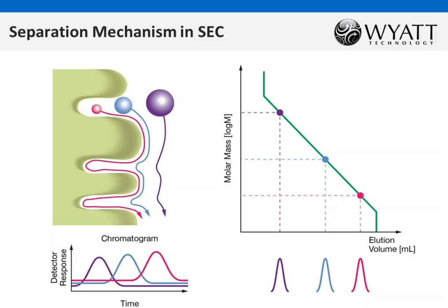Coupling SEC to multi-angle light scattering, however, overcomes this limitation. Since light scattering measures the absolute molar mass, we can now determine absolute molar mass independently from column calibration. We may also change the HPLC setup, such as solvents, column configuration, and detectors, without the need to recalibrate.